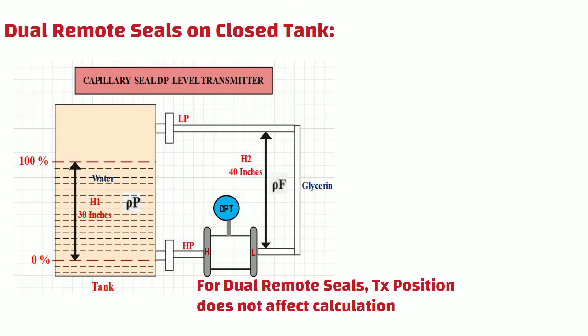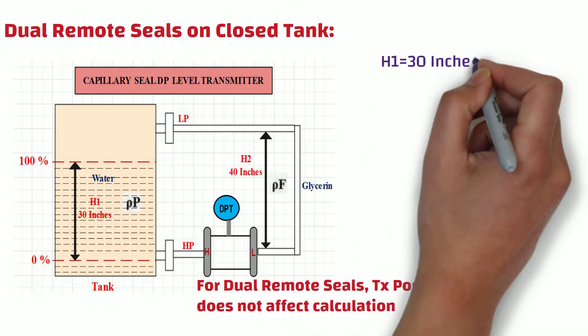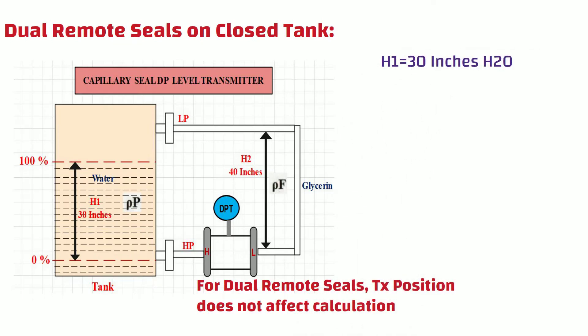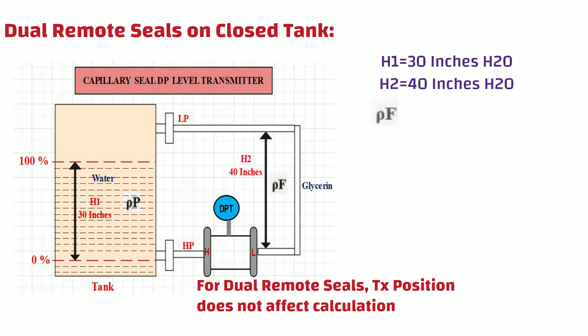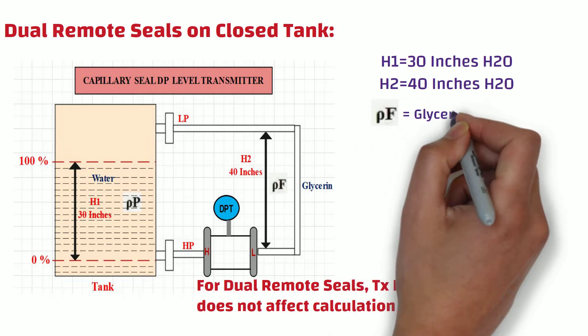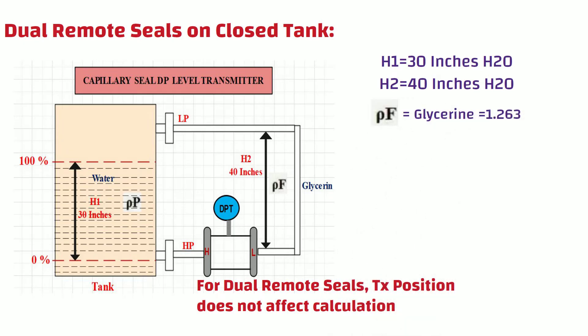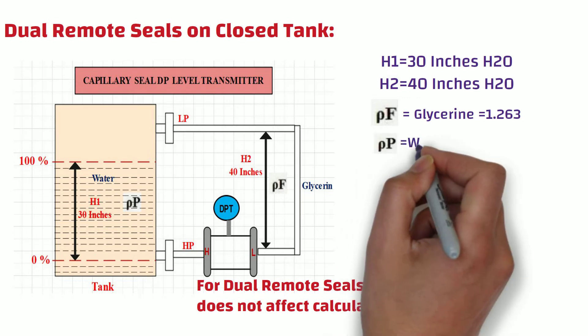As you can see, in this example, the distance between bottom tap and maximum level height is 30 inches, and the elevation distance between lower seal tap and upper seal tap is 40 inches. In addition to this, the remote seal is filled with glycerin, and the specific gravity of glycerin is 1.263. The process fluid is water, and its specific gravity is 1.